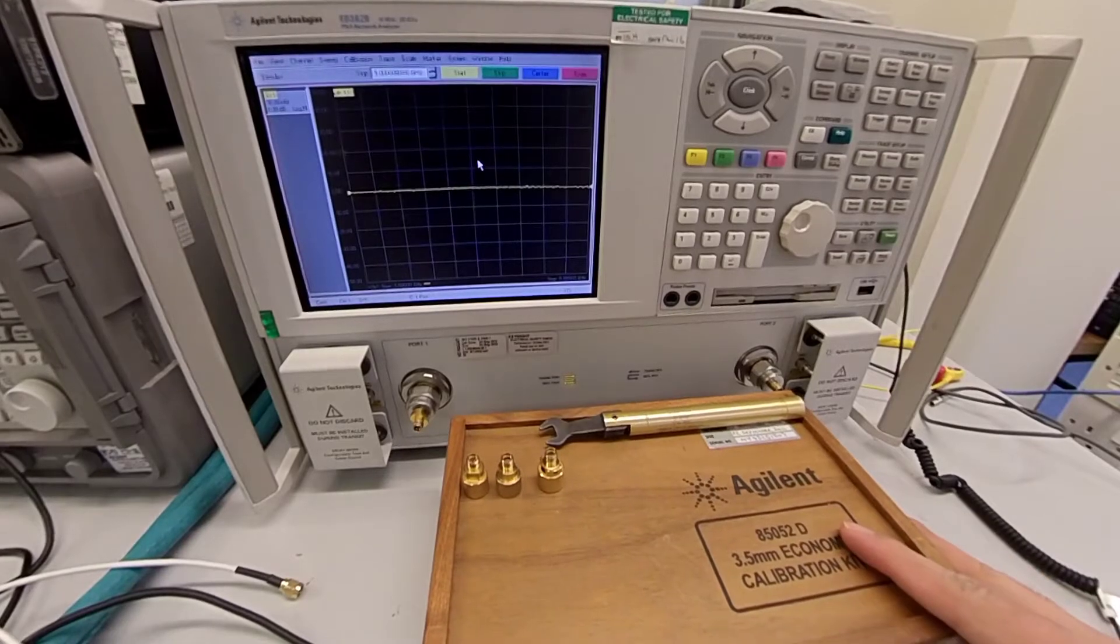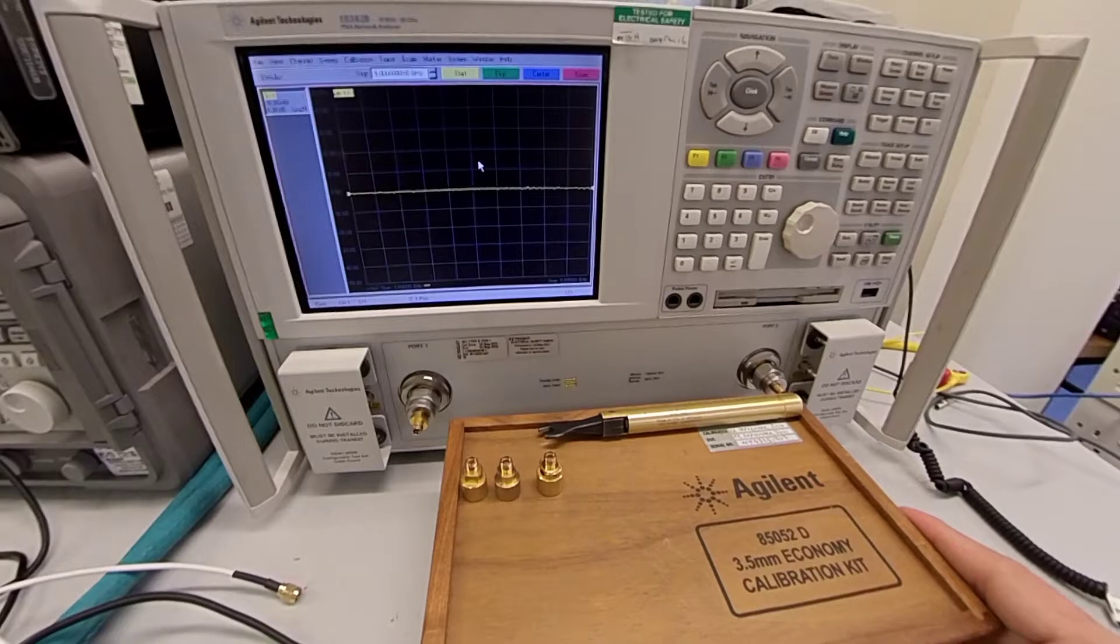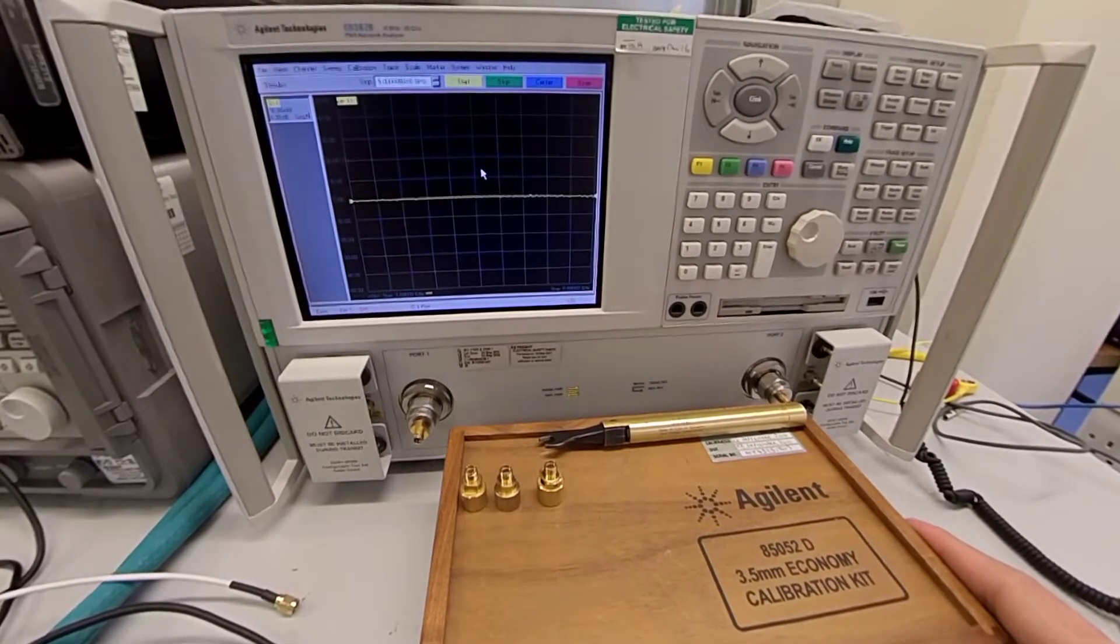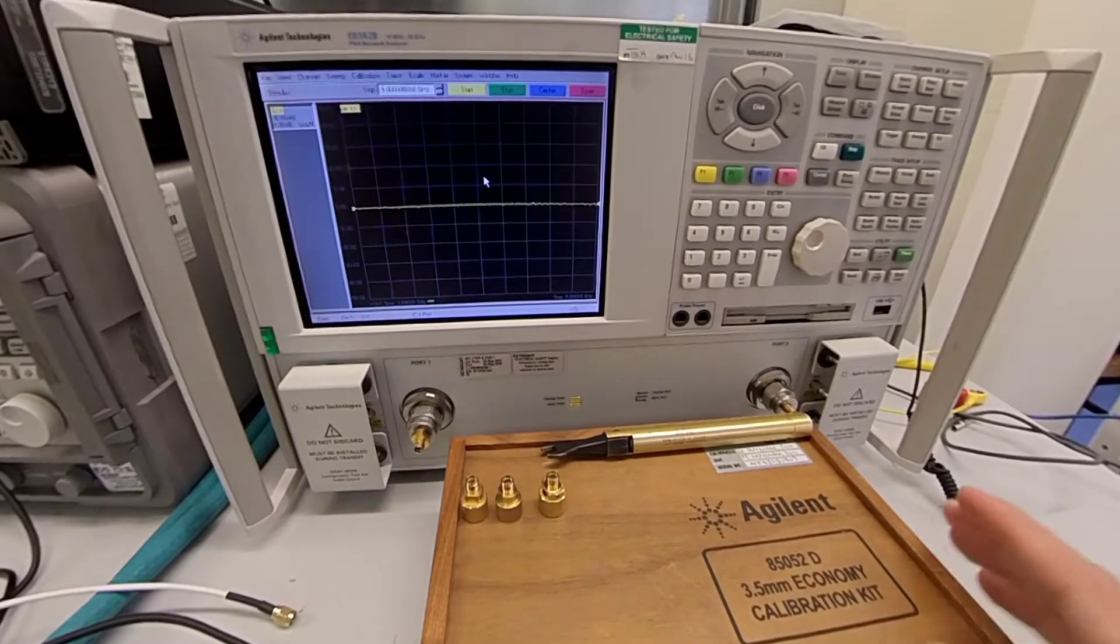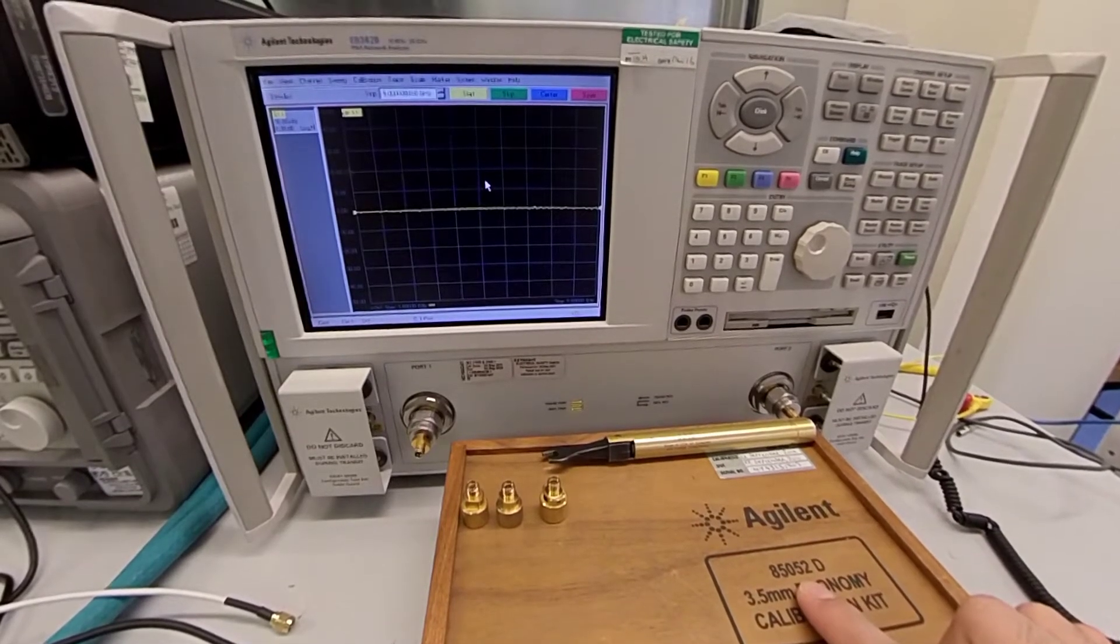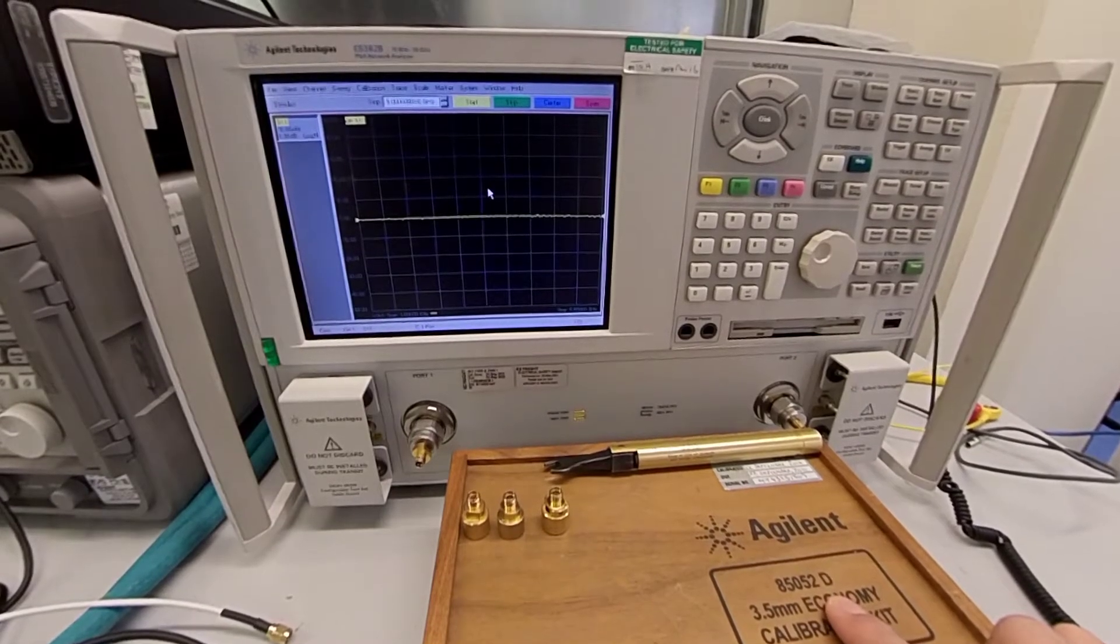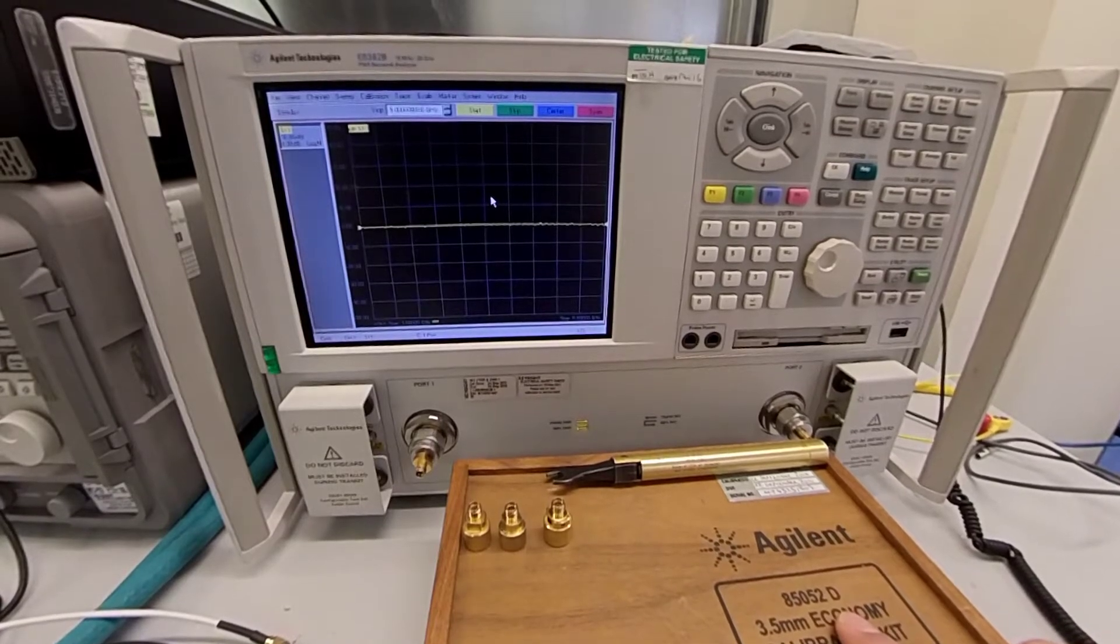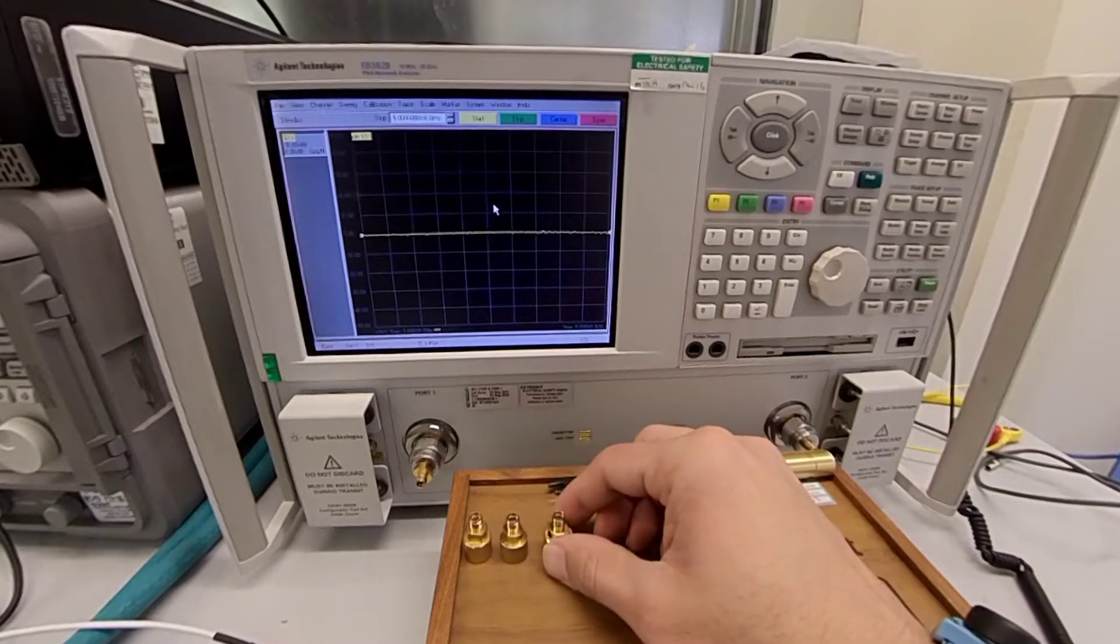In front of me you can see a mechanical calibration kit. Each analyzer is accompanied with a mechanical standard calibration kit. The model number for this kit is 85052D and we will select this model number when calibrating the analyzer. Each mechanical standard kit contains an open, short, and a broadband load.